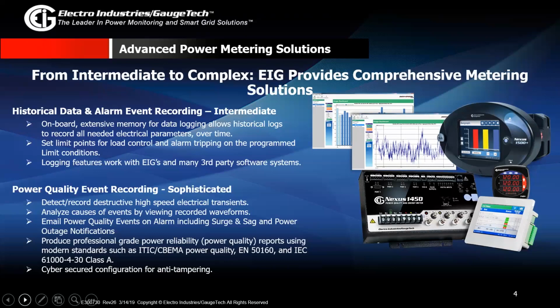There's also email on alarm capability. When you have a voltage sag, surge, or power outage, the meter will send an email notification telling you exactly what event occurred. This way your team can be proactive. When you get that email, you know that some sort of power quality event is happening on your line and you can take action against it.